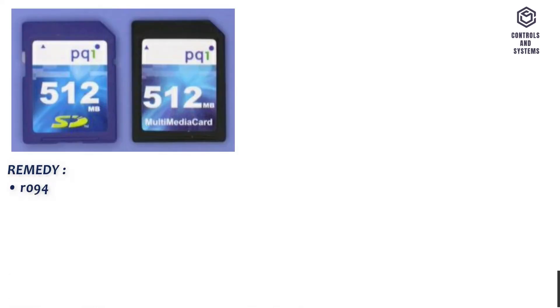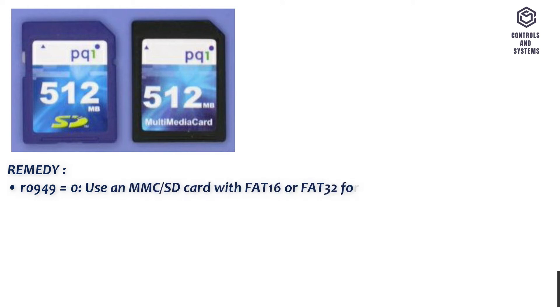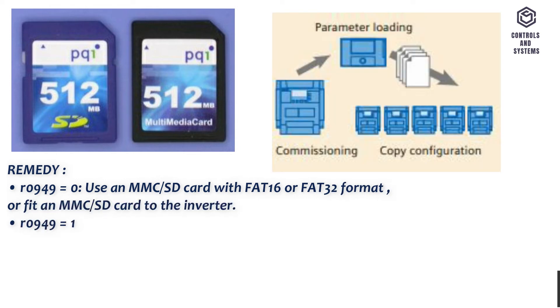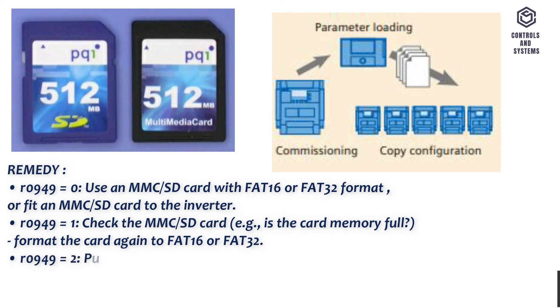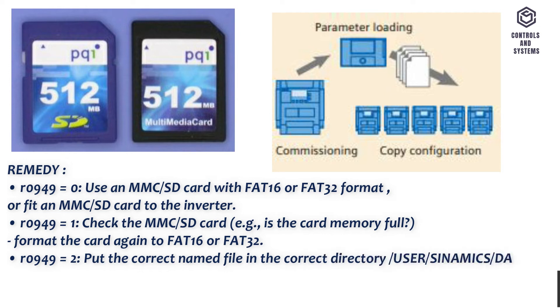Remedy: R0949 equals 0: use an MMC/SD card with FAT16 or FAT32 format, or fit an MMC/SD card to the inverter. R0949 equals 1: check the MMC/SD card — for example, is the card memory full? Format the card again to FAT16 or FAT32. R0949 equals 2: put the correct named file in the correct directory /user/sinamics/data.